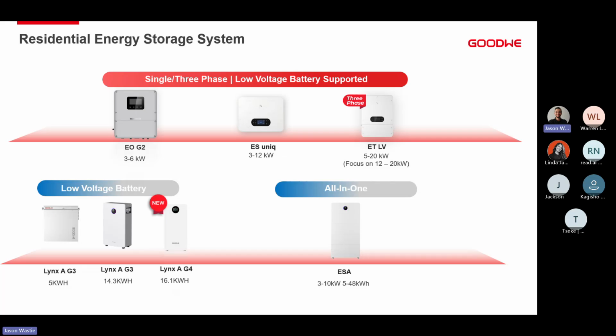Lastly is the ESA, or the all-in-one unit. The ESA is from 3 to 10 kilowatts, and then we can stack the batteries up for between 5 and 48 kilowatt hours, so up to 6 stacks, and then we will be able to parallel the system to build it bigger and bigger as well. This has got DC-DC battery modules in, meaning we can mix and parallel old batteries and new batteries together, and we can scale the system up accordingly.